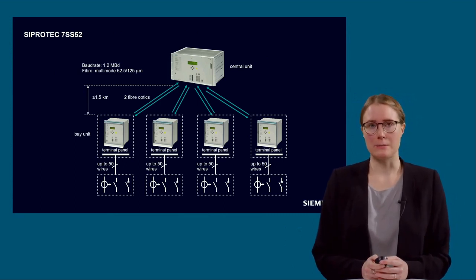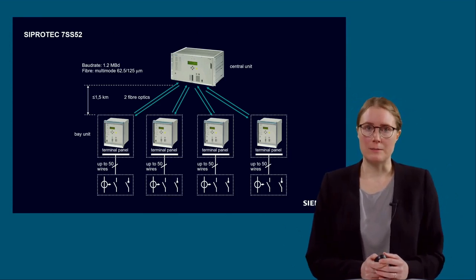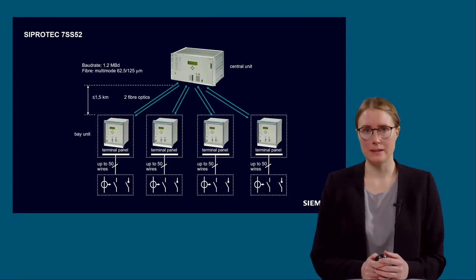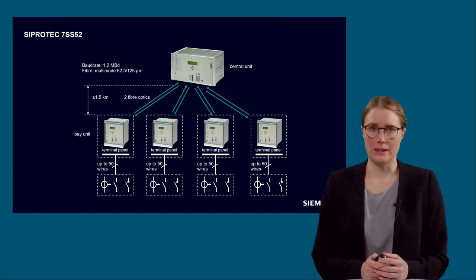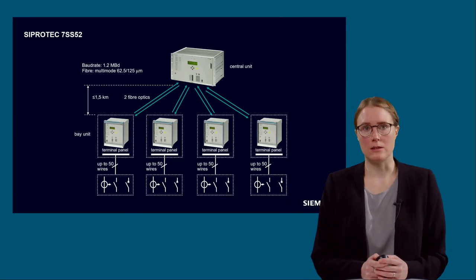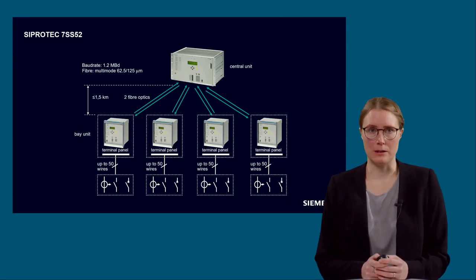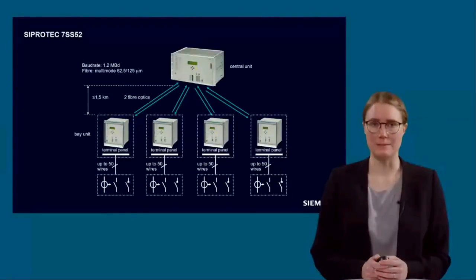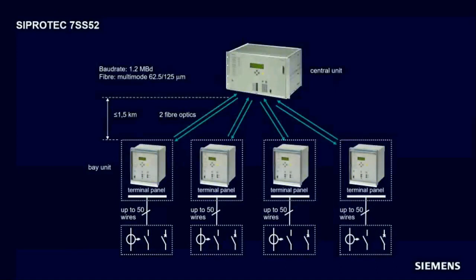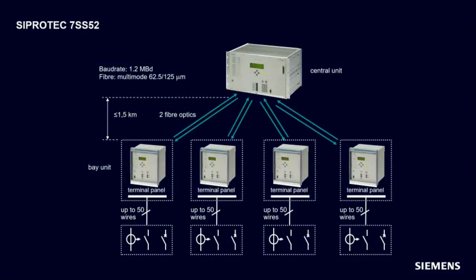The central unit in this case is based on the SIPROTEC 4 platform. The bay units are 7SS523 or 7SS525 devices, which are actually devices based on the SIPROTEC 3 platform. In this SIPROTEC 4 distributed approach, the bay units are connected via star connection to the central unit. The connection is done via multimode fiber optic cable. This is meant with the turquoise connection on the slide. The maximum distance between the bay units and the central unit is 1.5 kilometers. The protocol for the communication between the bay units and the central unit is the HDLC protocol. The measured value synchronization is done by the protocol, and no additional time synchronization is needed in the setup.